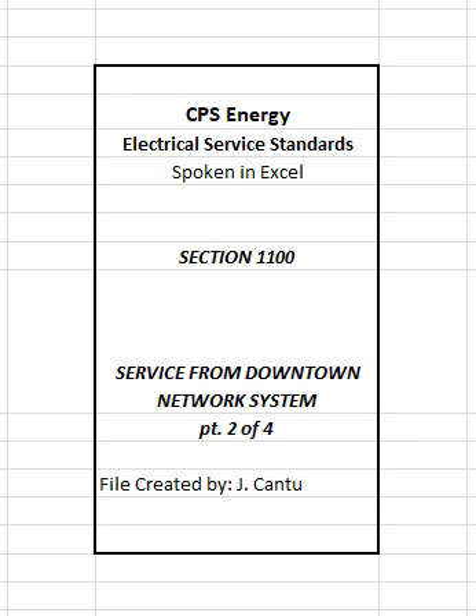3. Where required for installation and removal of transformers, transformer vault or room ceilings shall have removable, weatherproof slabs, sizes to be specified by CPS Energy. There shall be a 73-inch x 97-inch minimum slab or as specified by CPS Energy, and it shall be installed by customer as part of the transformer vault or room construction and completion.